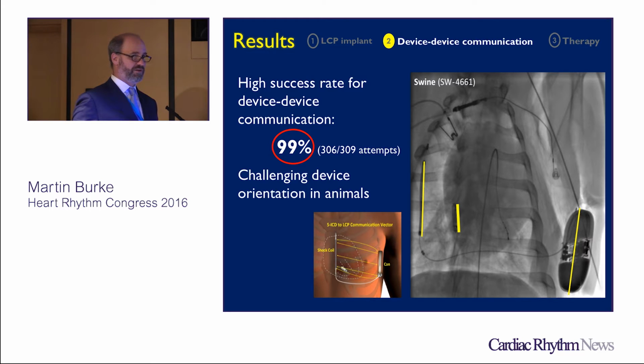And this is really the worst case scenario that we might see compared to a human model because the angle of the device is almost parallel to the electrodes that you're communicating from. And so the consequence here is to angle things a little bit differently. And these are studies that are ongoing for angulation so that we can give you some guidance when you're implanting these on exactly how they should be, sort of the most effective and safe way of communicating.